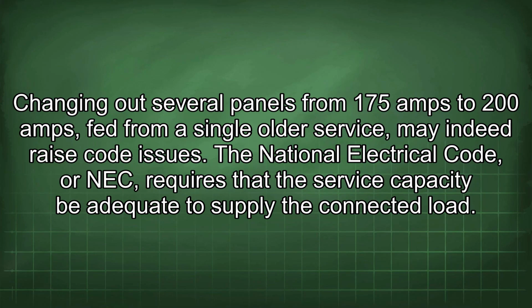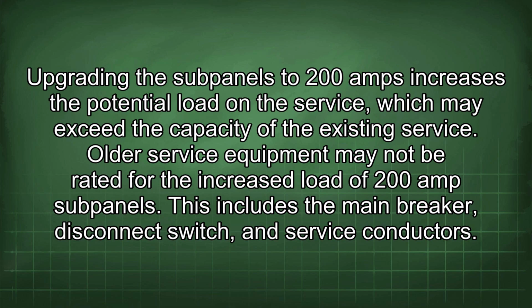Changing out several panels from 175 amps to 200 amps, fed from a single older service, may indeed raise code issues. The National Electrical Code, or NEC, requires that the service capacity be adequate to supply the connected load. Upgrading the subpanels to 200 amps increases the potential load in the service, which may exceed the capacity of the existing service. Older service equipment may not be rated for the increased load of 200 amp subpanels. This includes the main breaker, disconnect switch, and service conductors.